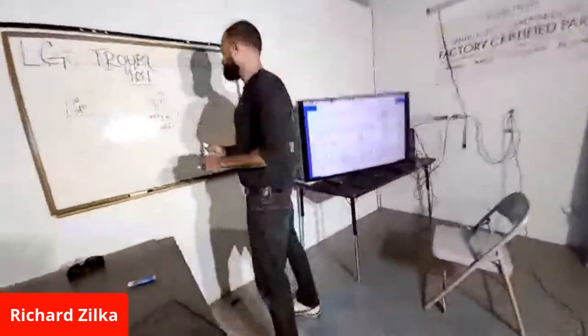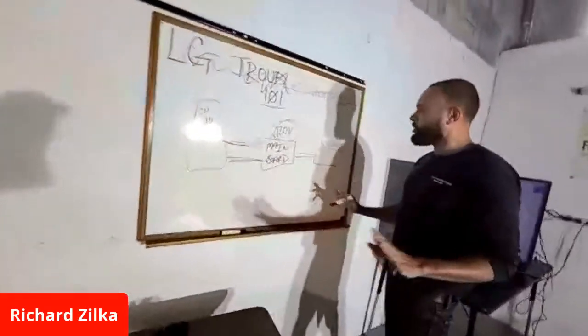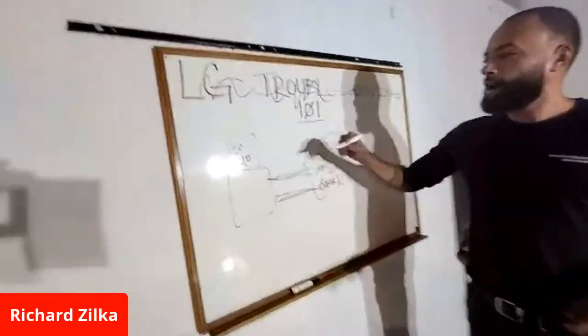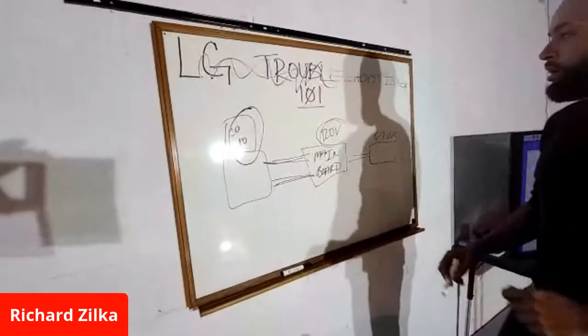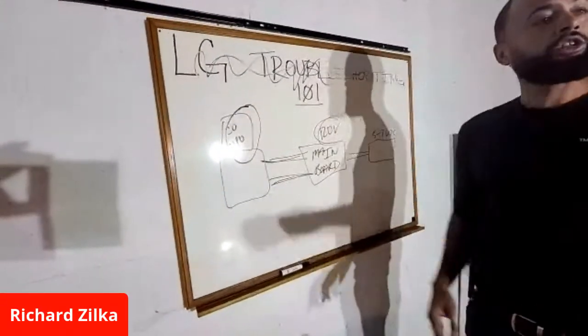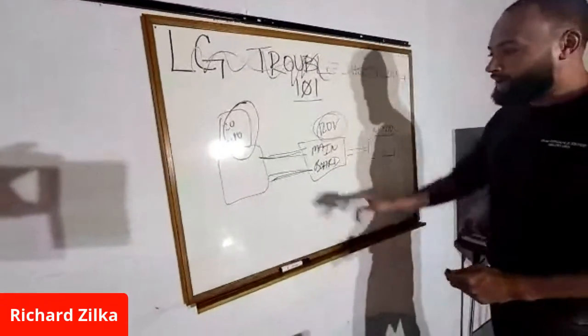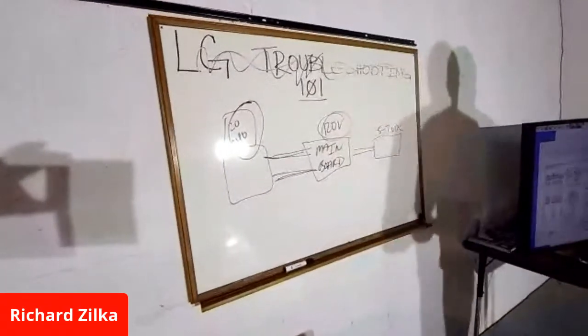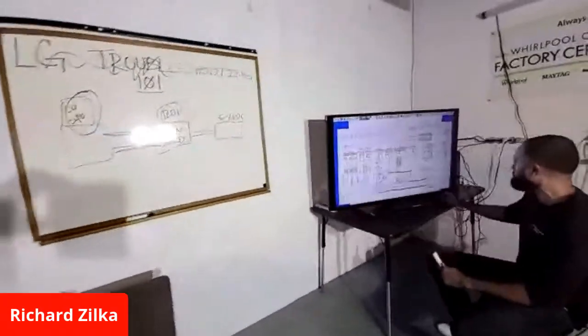So you didn't check the input to the user interface. The way you troubleshoot, you always verify correct polarity at the wall. Measure it down to your terminal block, which we did. After that, go to your main board, 120. Come over here and follow me.